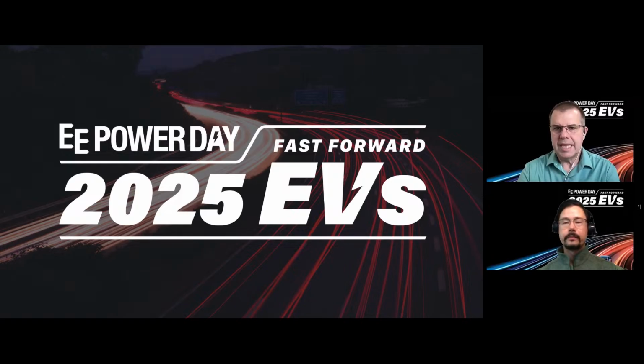All right. The first one here is asked by Matthew, and he's asking, what components would you expect to damage in the event the trip delay time is not fast enough? Good question. So this question ties into the coordination aspect of fuse design that we touched on in the presentation. The fuse has to open before damage is sustained to anything downstream.